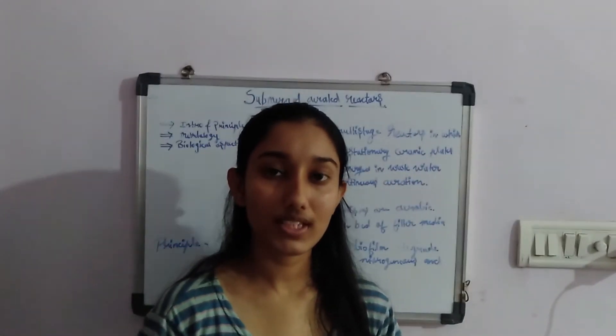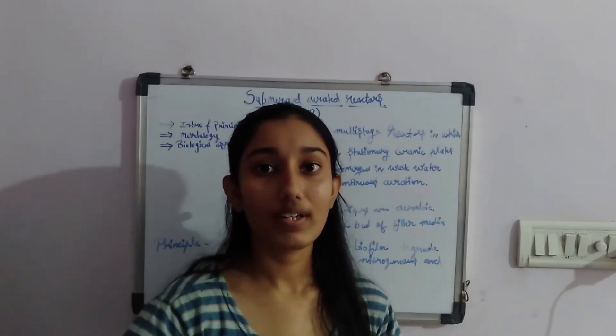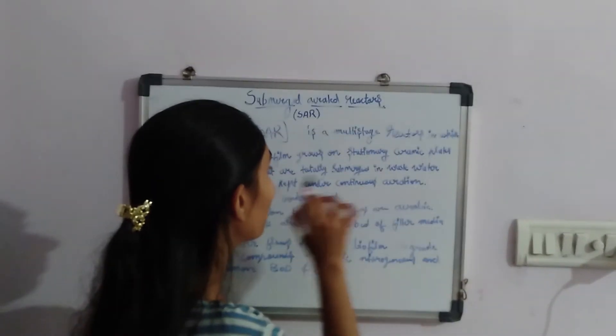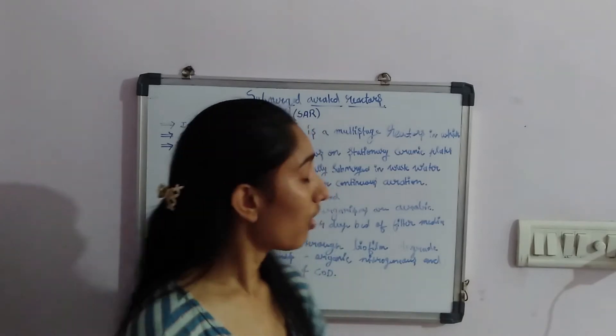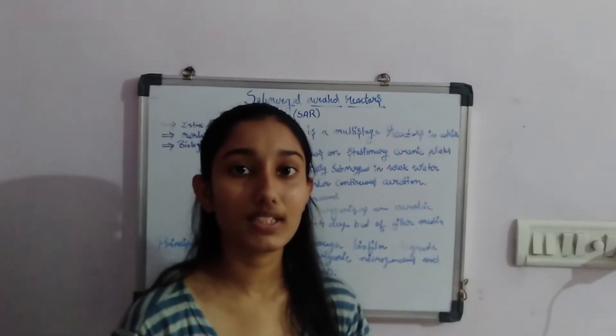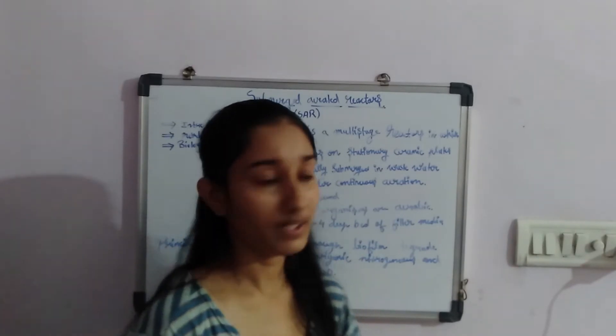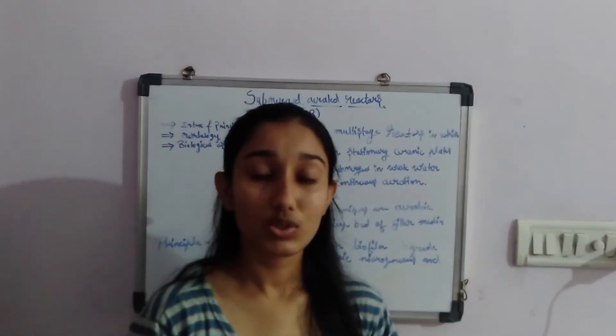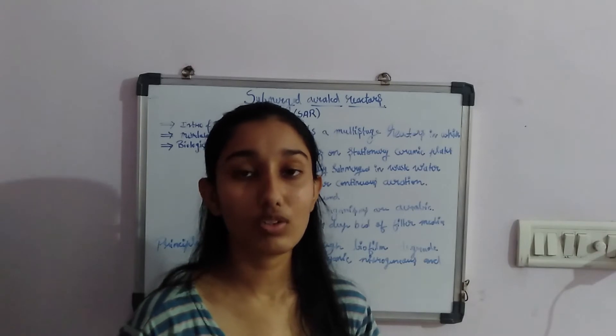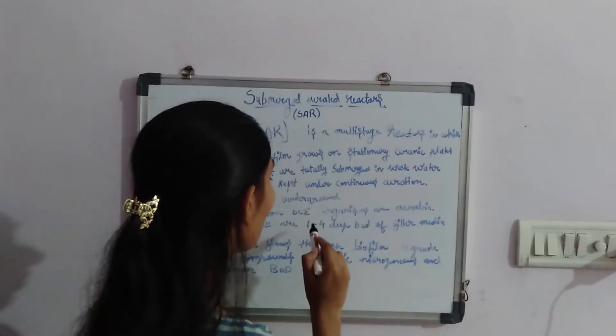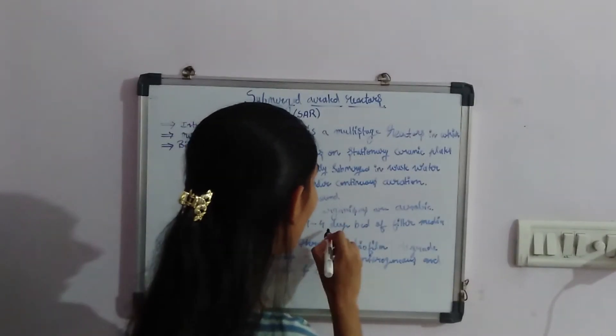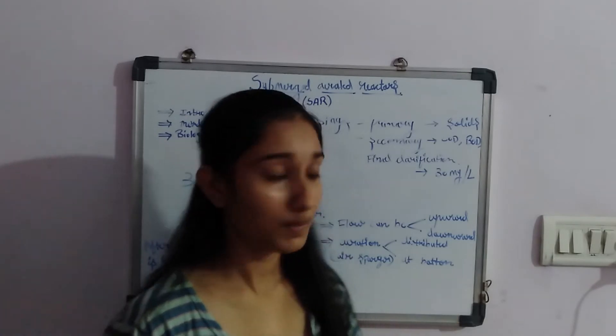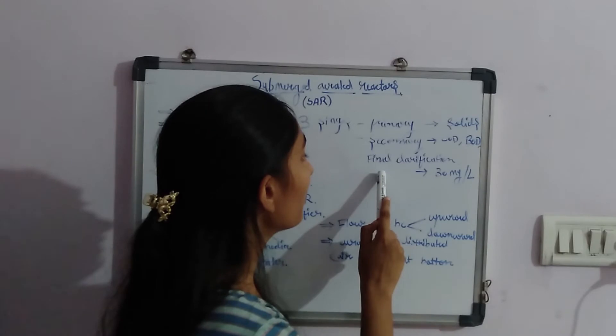Aeration is required because the organisms involved are aerobic. The biofilm thickness is 1 to 4 mm. In terms of methodology, this is a multi-stage process with 3 different stages: primary, secondary, and final clarification.